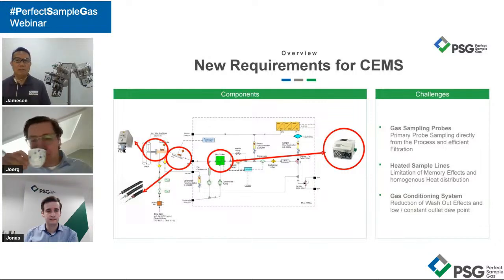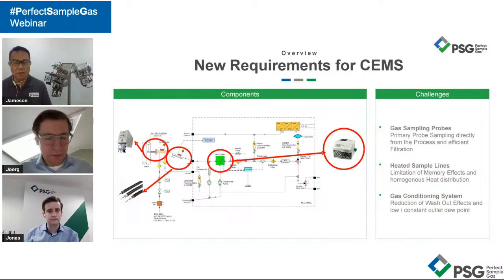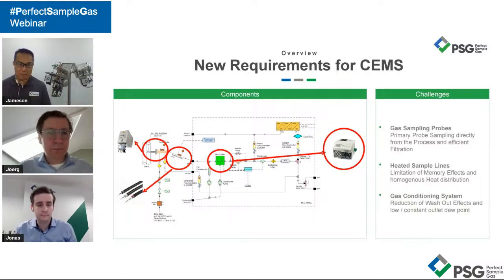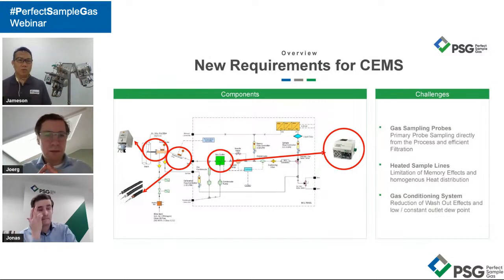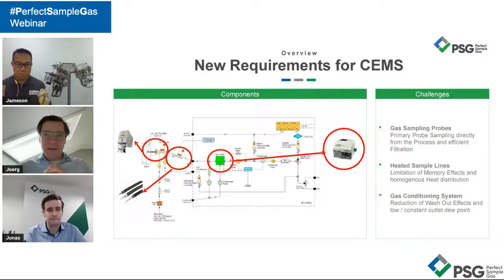We want a thermodynamic reaction to take place in the gas cooler. And that is why many people make mistakes with the long, naked, unheated Teflon tubing before it goes into the gas cooler. This is one of the mistakes. So making sure that it goes right into the cooler removes the water very effectively before it goes to the other accessories, before it reaches the gas analyzer. So, three major components.